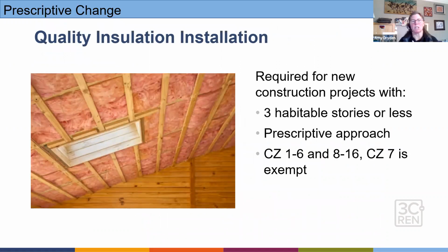So quality installation is now required for new construction projects. Again, looking at a height limit here for 3 habitable stories or less. So it's going to be really hard to trade this one off, which means you'll be seeing it more in the performance approach. And we'll be having more HERS raters out on multifamily buildings. You can see there climate zone 7 is exempt, just because of lower loads. And just again, calling out, this does not apply to the 4+ stories, only for 3 habitable stories or less.